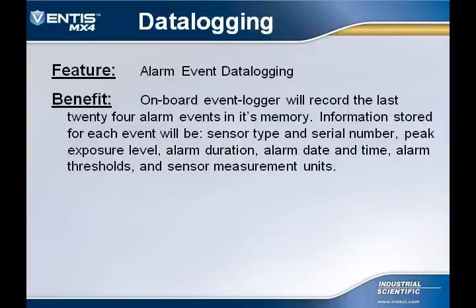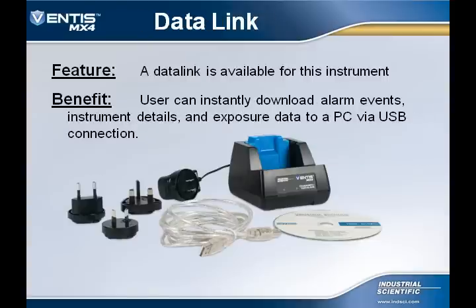The Ventis MX4 has alarm event data logging. The instrument will record the last 24 alarm events in its memory. Information such as sensor type, serial number, alarm thresholds, alarm date, alarm duration, and peak exposures can be recalled. A data link accessory is available for this instrument, allowing the user to easily download data, alarm events, and instrument details directly to a PC using a USB connection.